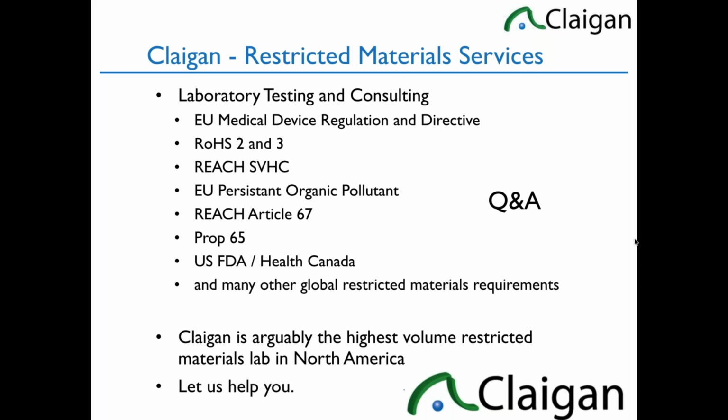This is a good question. Does the first section of 10.4.1 apply to all MDDs or only those in body contact? It applies to all MDDs. This is the one about degradation products, but the ISO standards will focus very heavily on the ones where you could have a human exposure. If the degradation product won't get into the humans, it's not an issue.